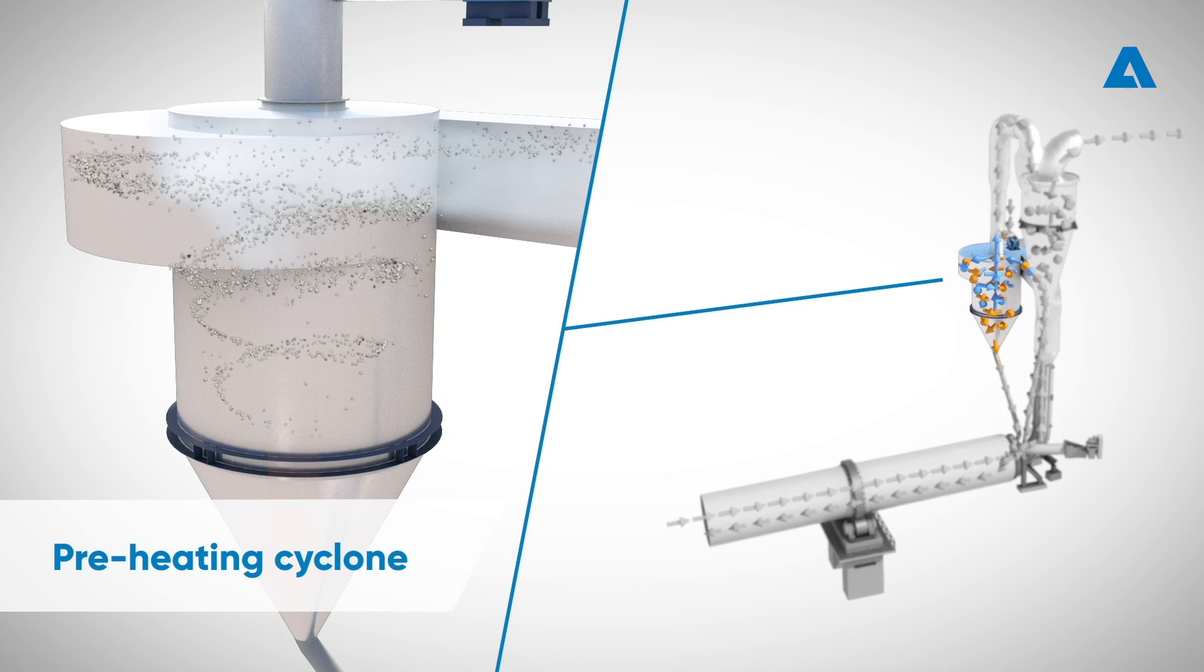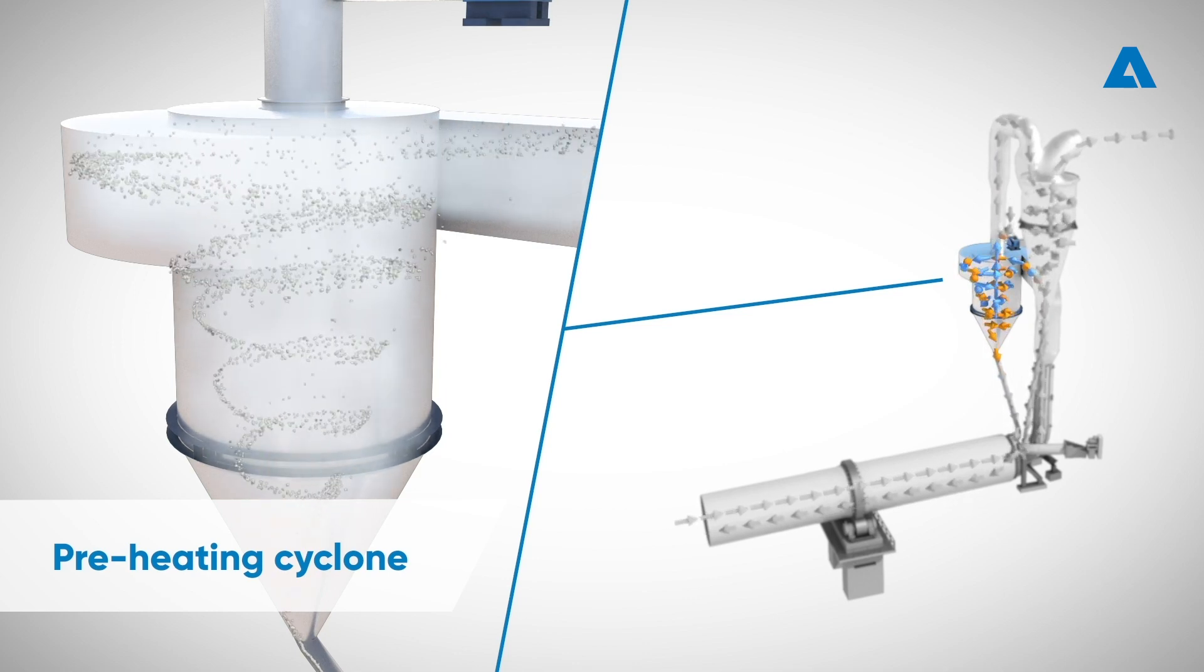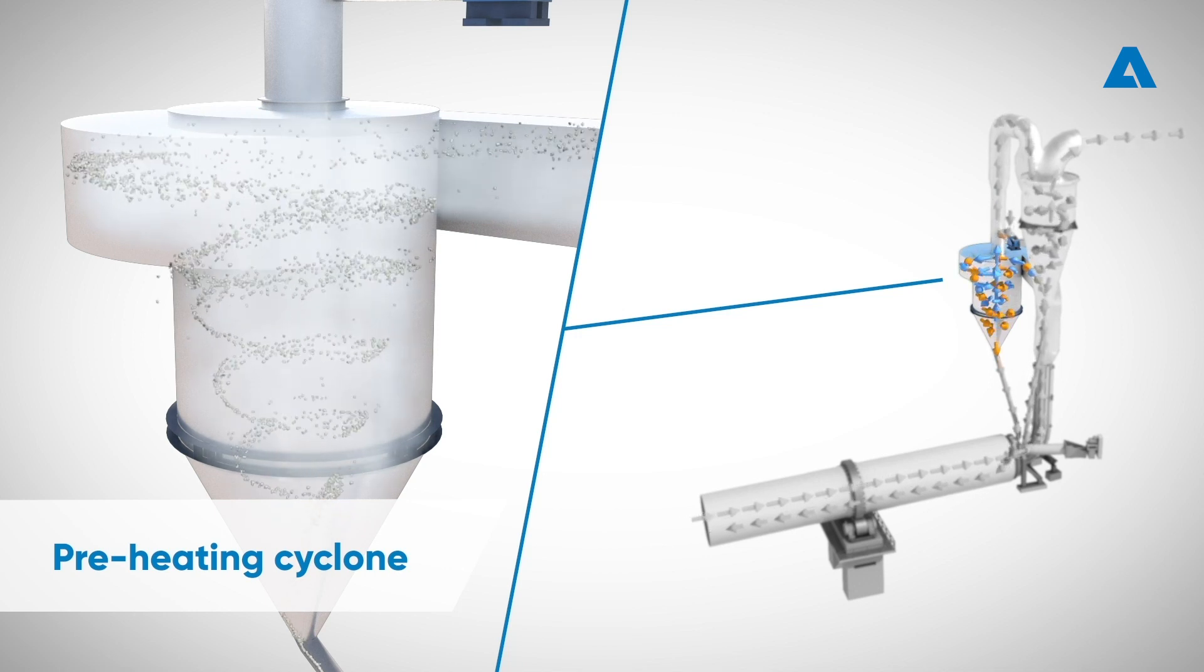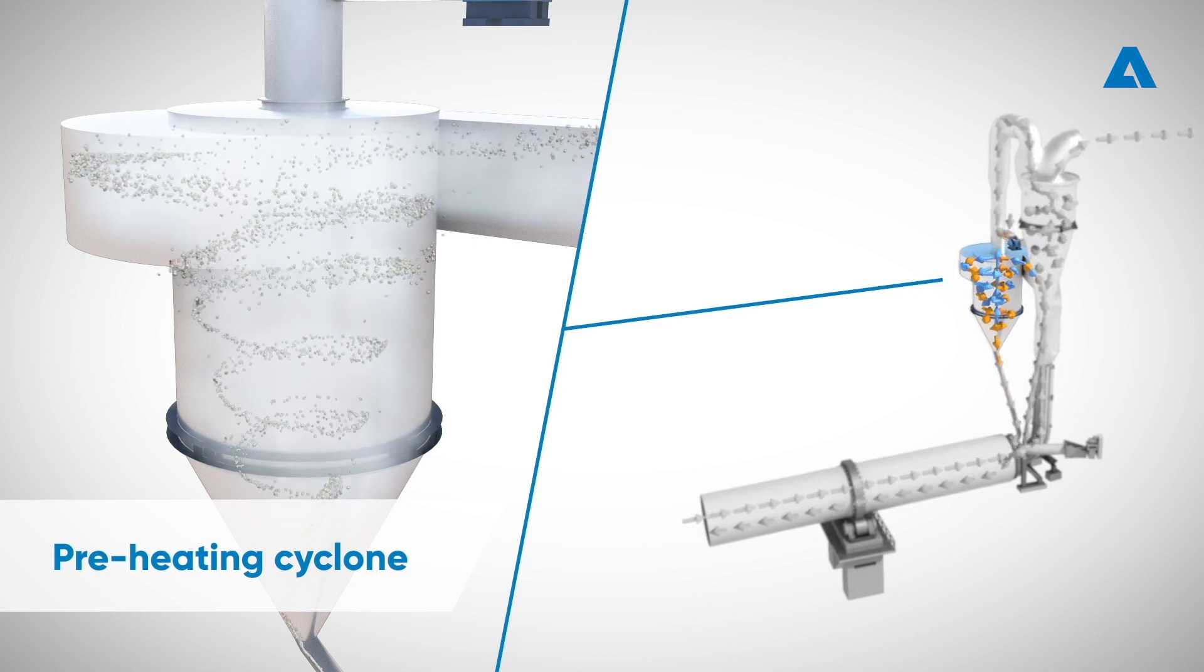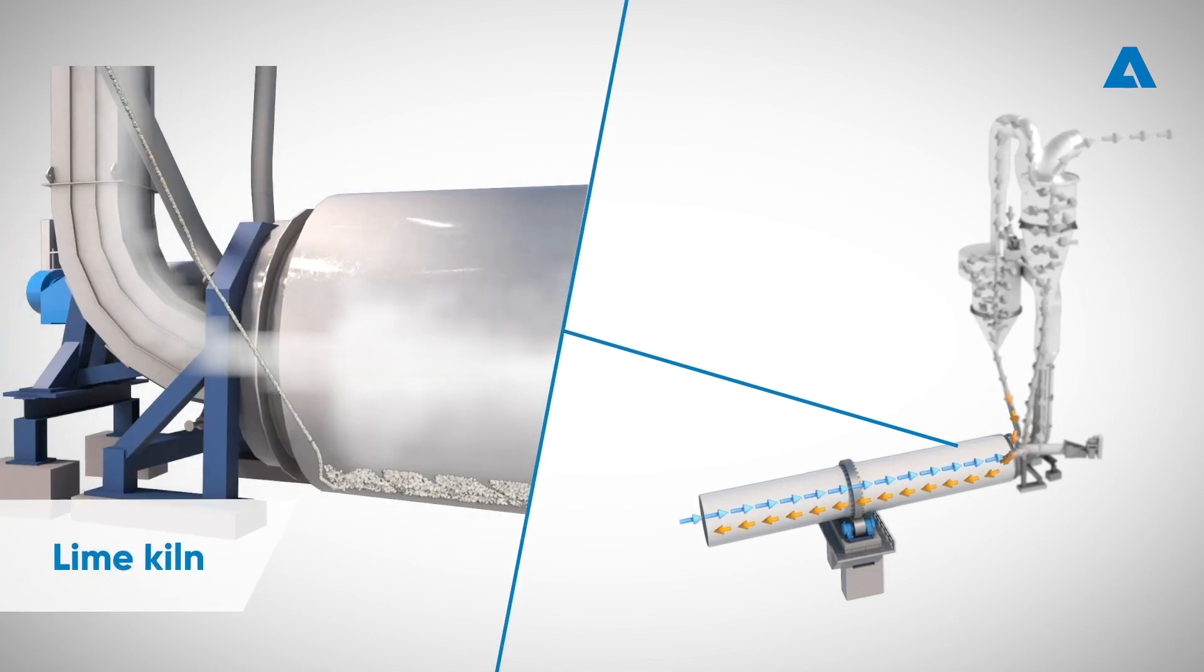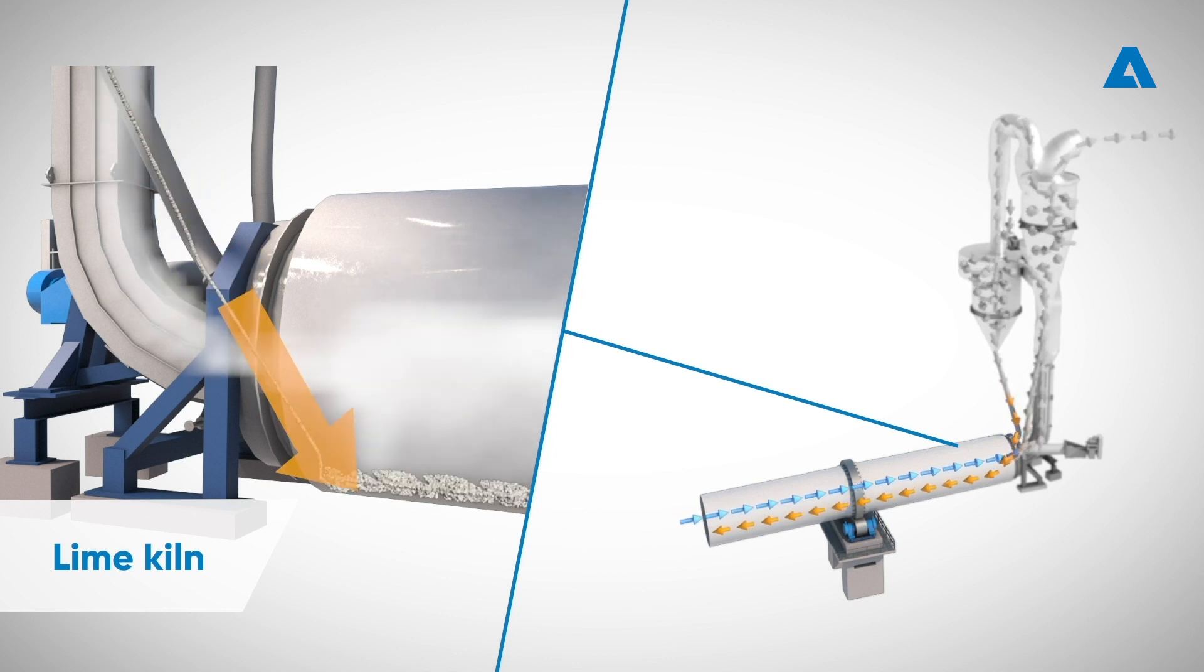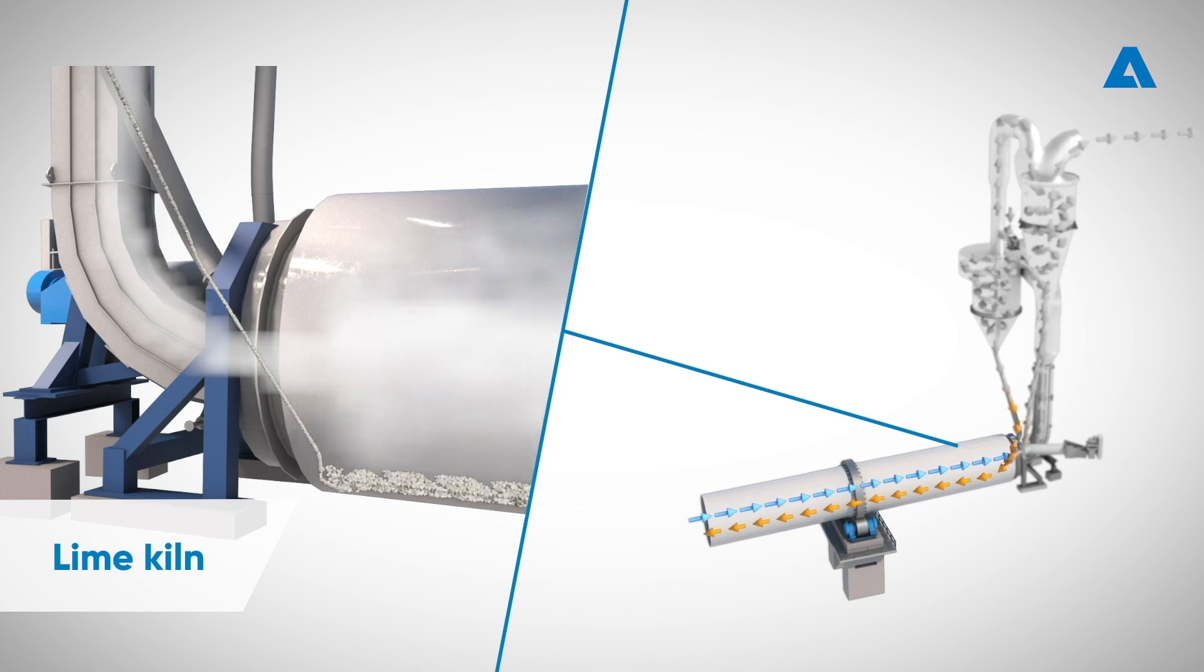The preheating cyclone separates the heated lime mud from the flue gas. The calcination process starts and lime mud flows by gravity through a chute entering the rotating lime kiln. Due to the higher temperature of the lime mud entering the lime kiln, the calcinating process continues with better energy efficiency. This means higher capacity with a shorter lime kiln.